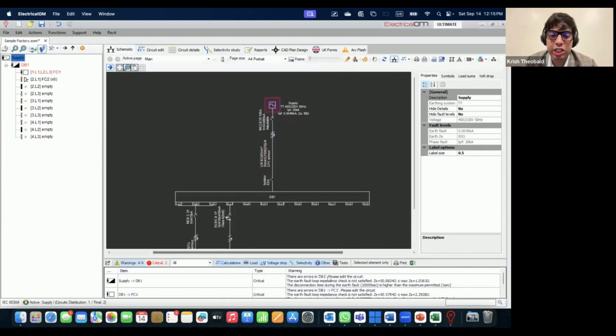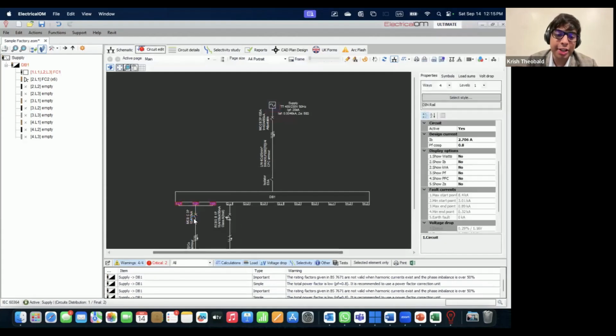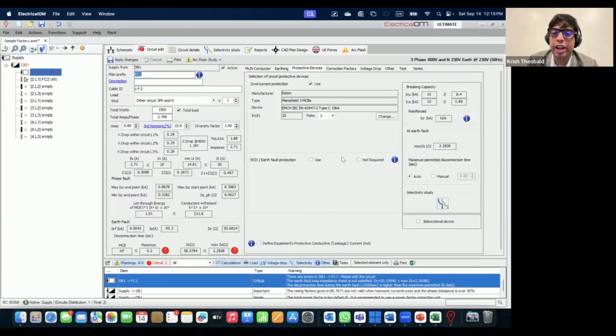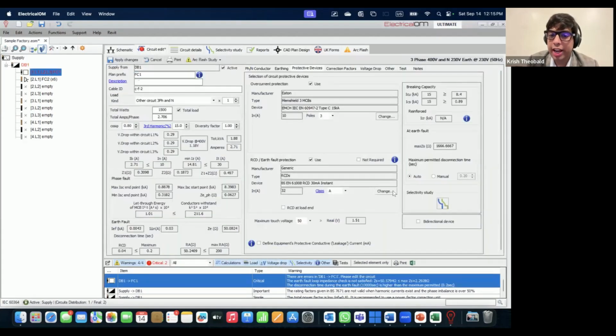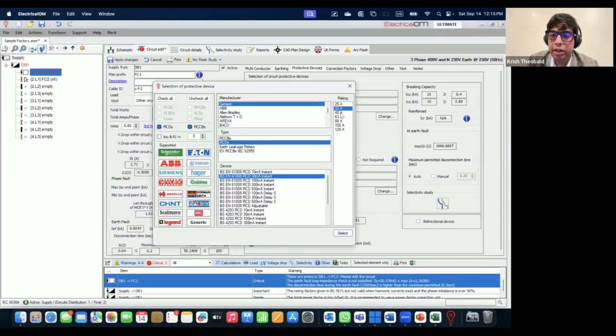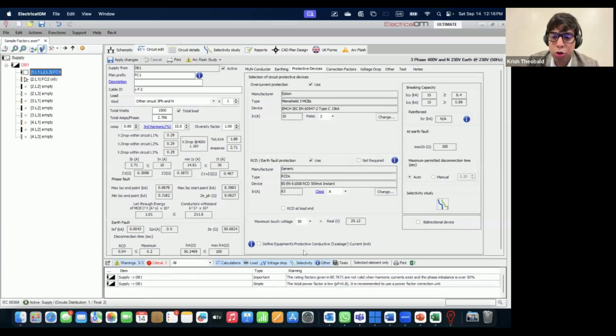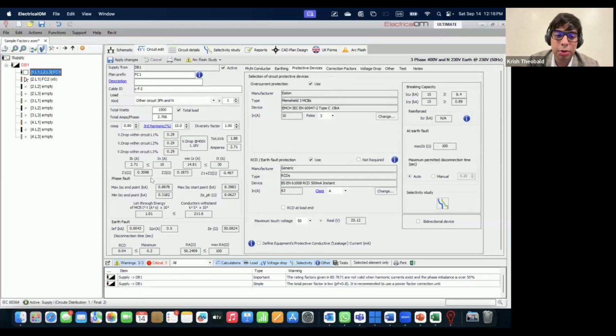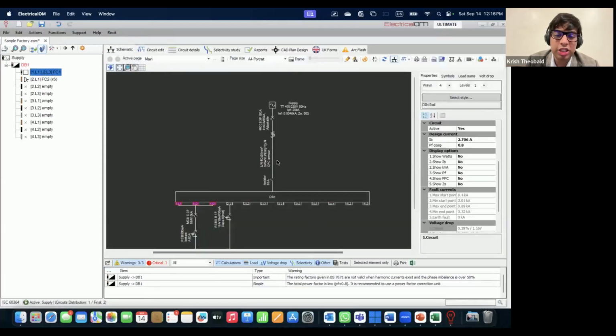Now, see if I 50 volt, now again I'm getting an issue. So it's saying that this circuit cannot disconnect. So then I need to add an RCD. Say I add an RCD, make it, I don't know, say a 63 ampere RCD with 500 mA. Then that warning will now go away. So essentially that's how it works.